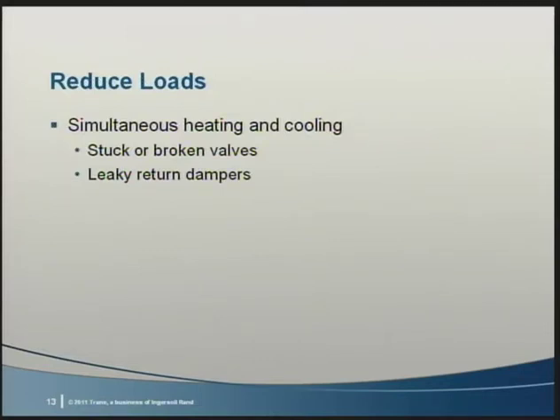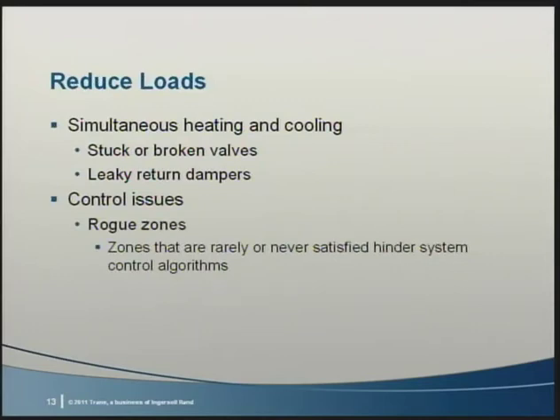One study by Lawrence Berkeley National Labs showed leaking return air dampers adding 46% to the required cooling energy and 6% to heating energy. Control issues are common. Look for rogue zones that do not respond to control or have vastly different needs than other areas on the same system. It could be that the design was inadequate, the sensors are inaccurate, or the set points have been modified. Rogue zones need to be identified and addressed because they'll almost surely waste energy.